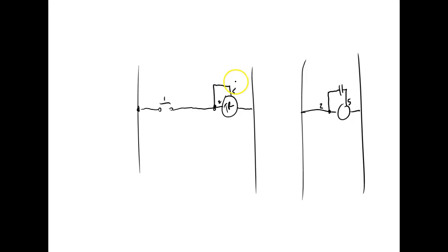So this is the easiest way to do an on delay timer. Now the off delay timer, we would have to do it this way. We would literally have to come over here and have a contact between here and here. So if they tell you it's an off delay, we would have to control this with a contact. But this is for what type of timer? On delay. So when we close that button, we put power on 2, but we also put power on 5, which tells it to start what? Start timing. So the on delay is real easy. All you got to do is make sure you jump between what? 2 and 5. And after that, on delay. Off delay, though, you're going to have to control it with that contact.